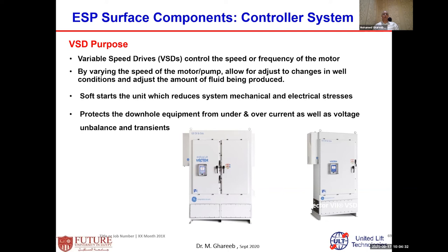Instead of using a soft starter with a switchboard, the variable speed drive is already equipped with a soft starter. You can start your well in a very soft way, at a very low speed, a very low frequency, which can extend the running life of the motor shaft and reduce the mechanical stresses over the shaft of the motor, the seal and all the others. It protects the downhole equipment from undercurrent and overcurrent. If there is undercurrent or overcurrent, I can adjust and rebalance using this.